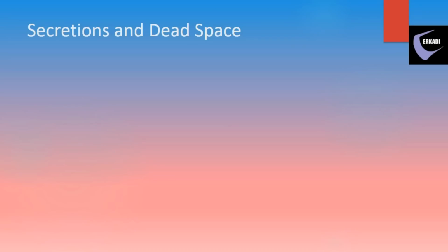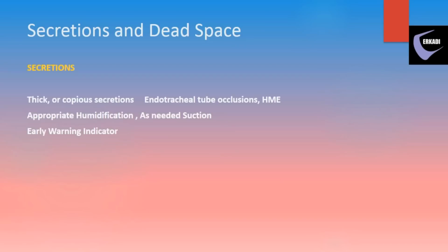Two issues are sometimes brought up in relation to patient proximal sensors, that they might cause problems in patients with secretions and that they might cause problems because they add to the dead space. Let us look at these individually. An issue that has been discussed in the context of proximal flow sensors is the possibility of occlusion or malfunction of the sensor by copious sputum production.